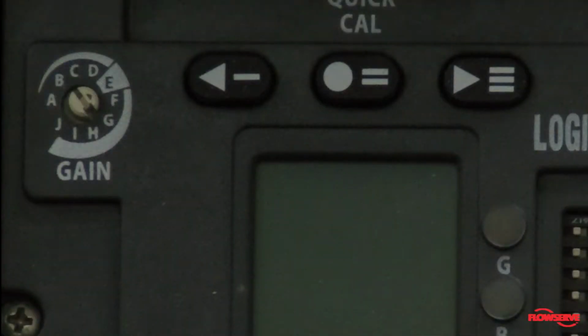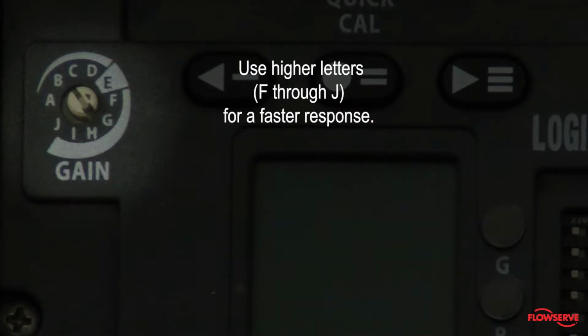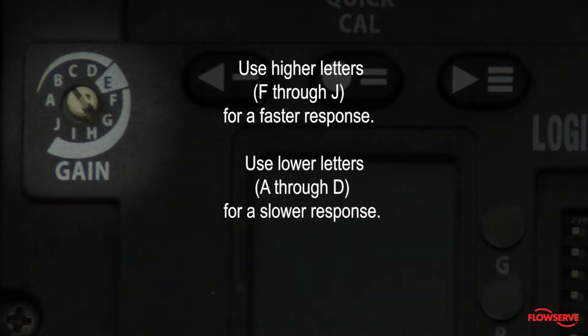For fine-tuning the positioner, use the gain dial to adjust the response. With auto-tune enabled, setting the gain at E typically creates a good balance between the speed of the stroke and accuracy. For a faster response, use higher letters, F through J. For a slower response, use the lower letters, A through D. The small arrow on the dial, not the slot, must point to your desired setting. With the auto-tune off, refer to the manual for configuring this setting.